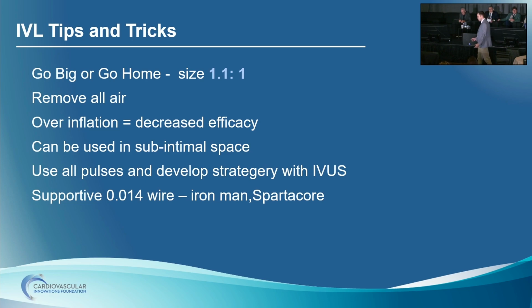You can use it in the subintimal space if you have to. You're getting the device out, so you use the whole device, okay? Don't just use 40 impulses after one treatment because you think it looks better. The more you can cause microfractures throughout this calcium, the better vessel compliance you're going to have as a whole. The other thing is that the way the emitters are designed, they do send out these high frequency pulse waves, and the goal is for them to overlap, but that's not perfect.